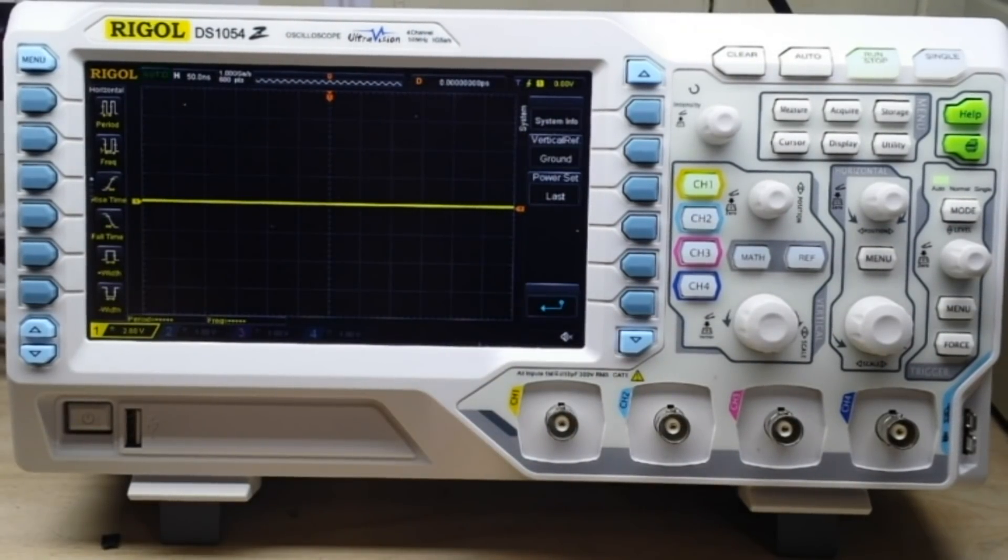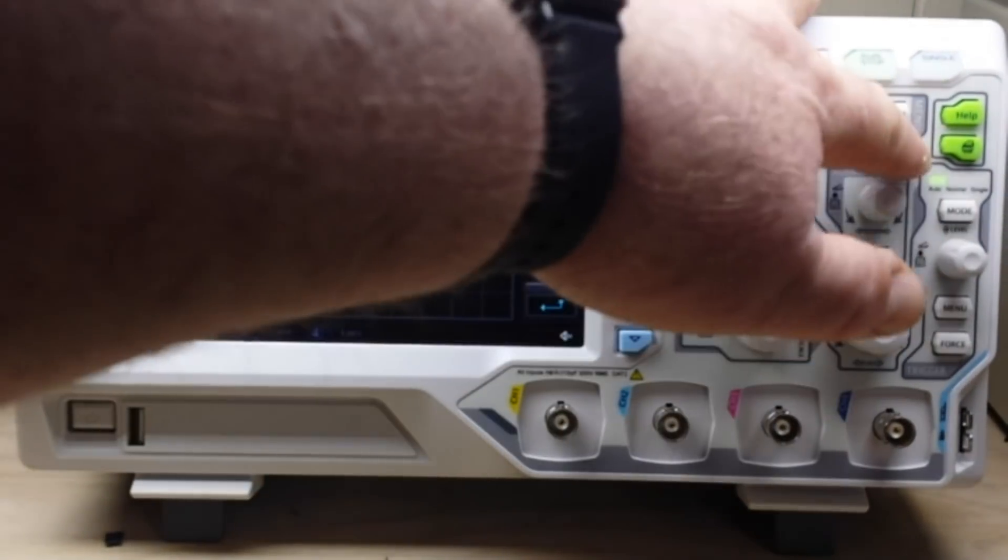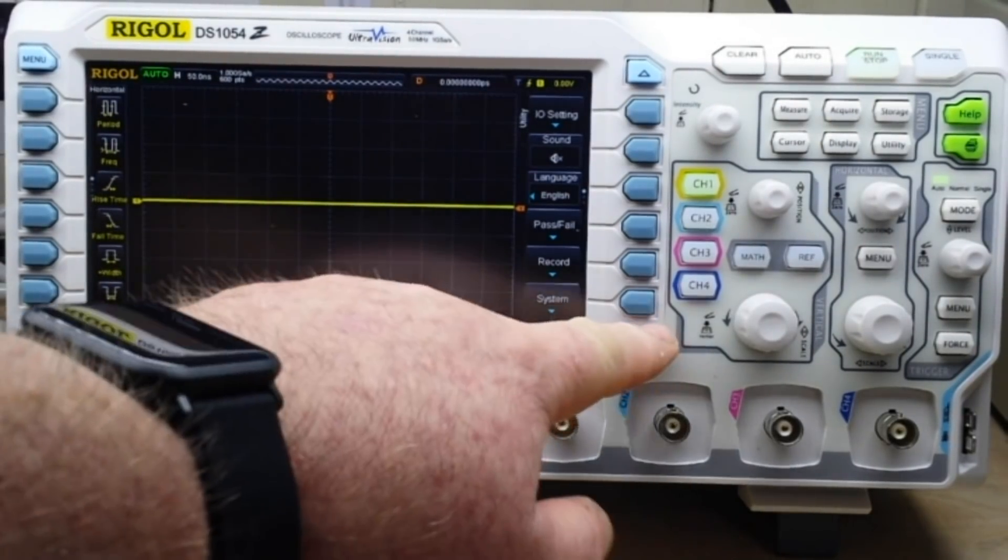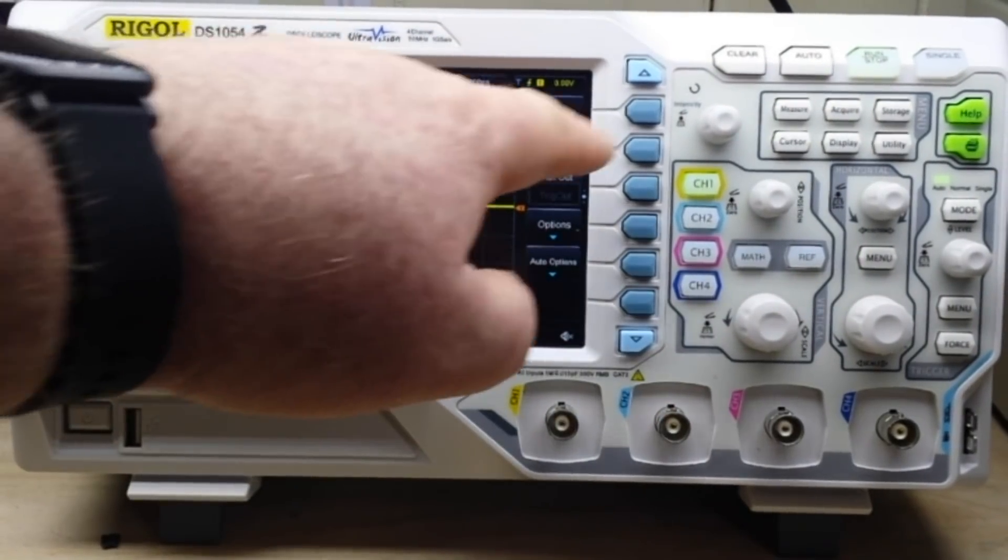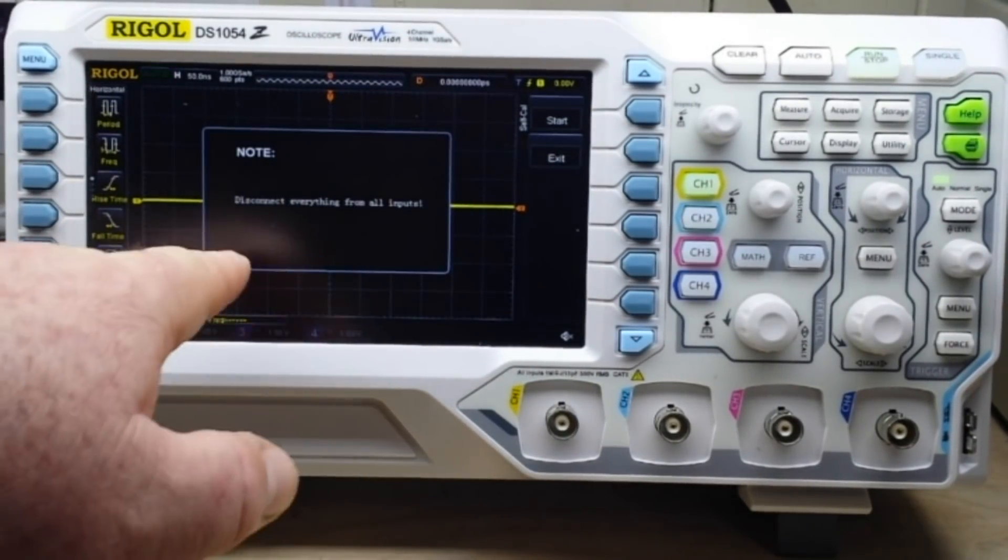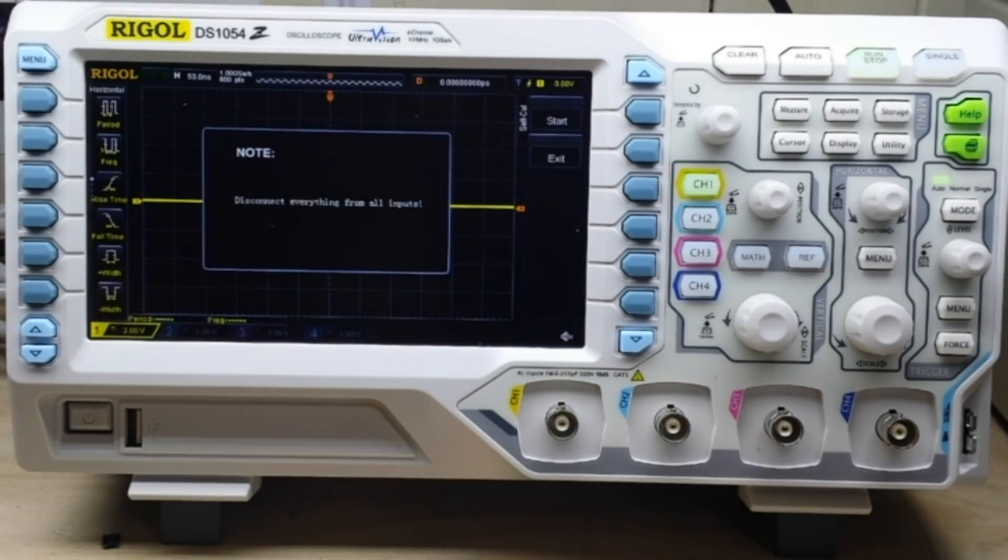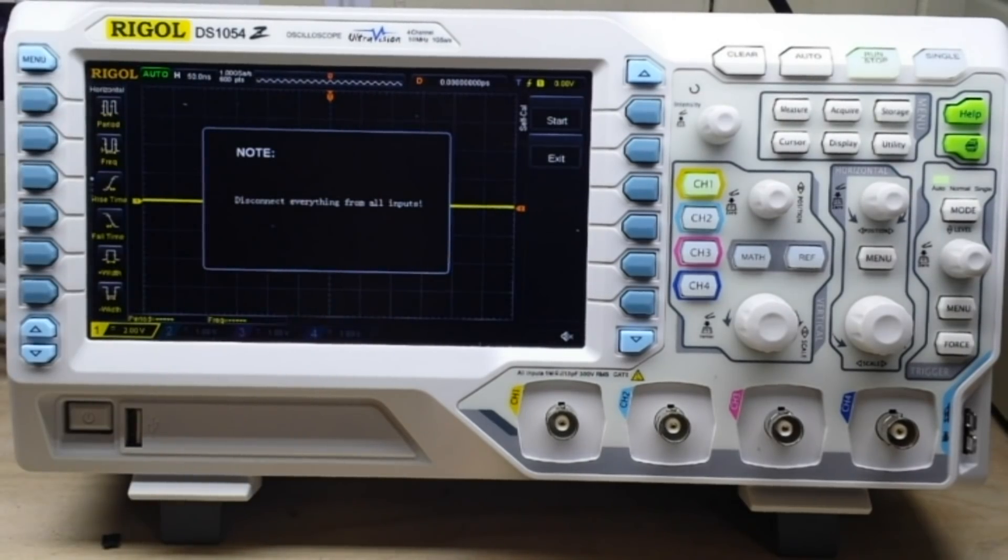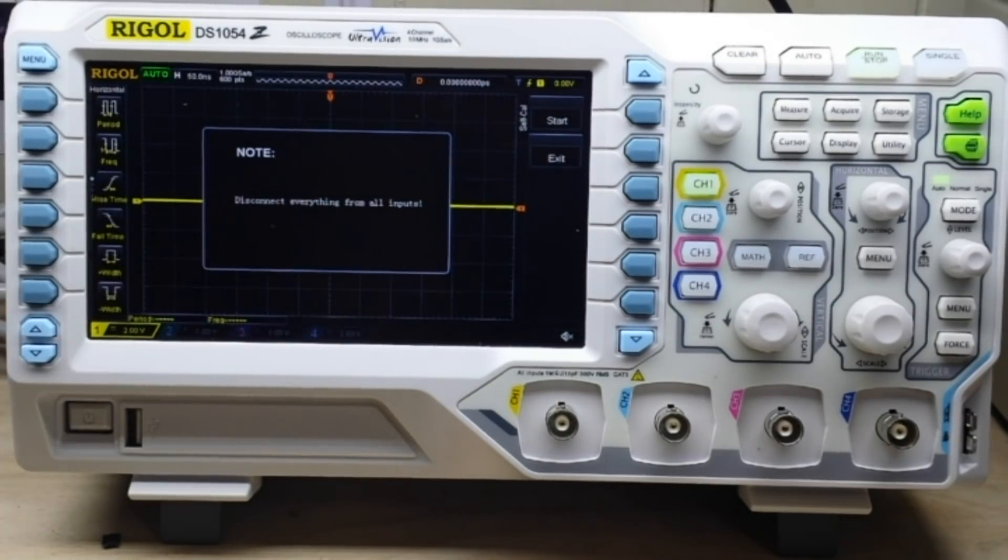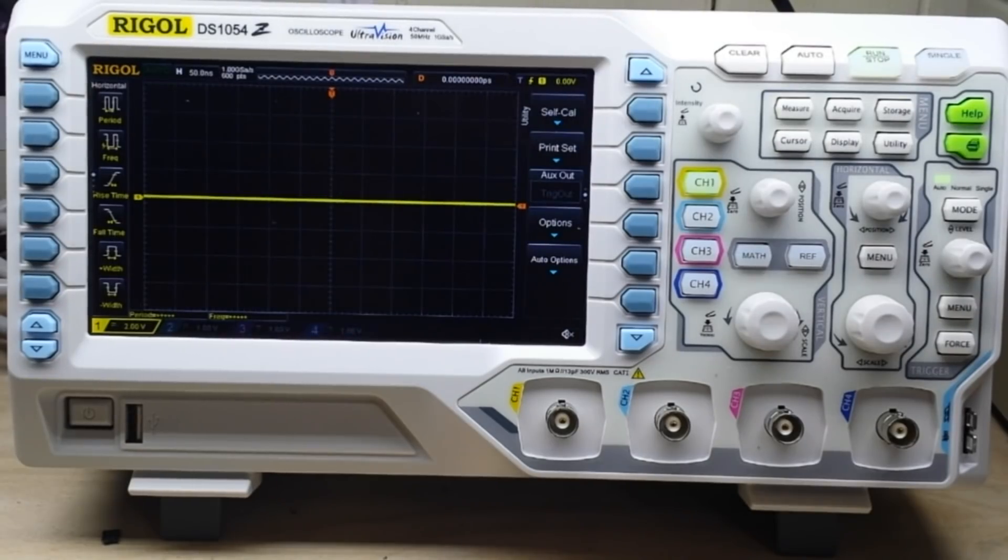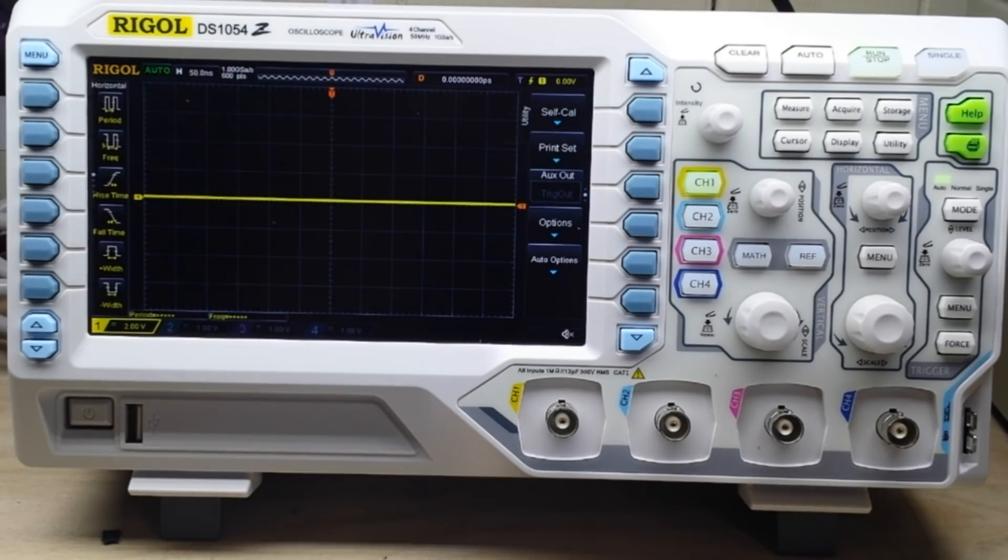There we go, self-cal. So we're going to hit the self-cal. It says disconnect everything from all inputs and then hit start. Now depending on your scope, this can take anywhere from two minutes to 45 minutes, so go get yourself a cup of coffee or something. Hit start and come back when it's done.